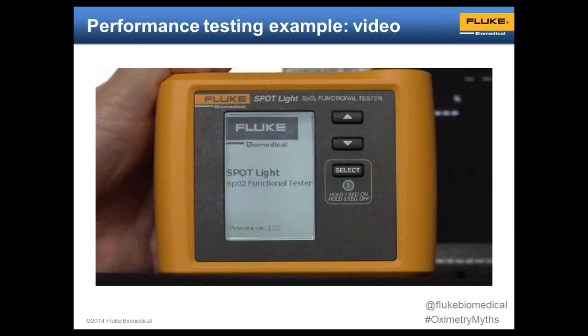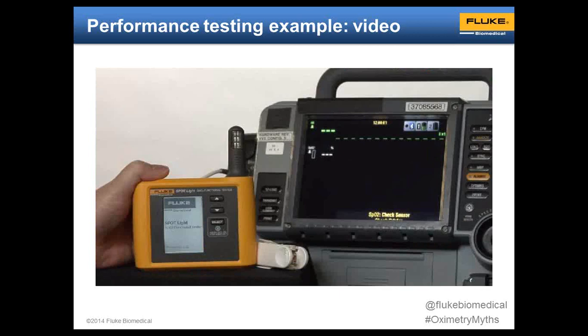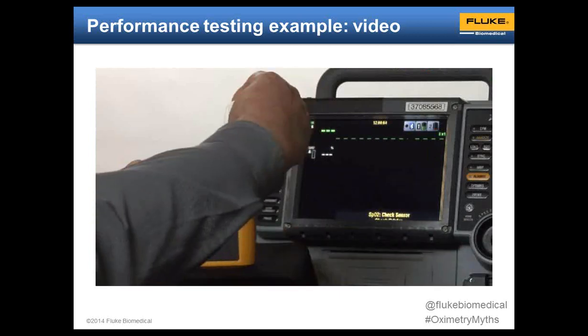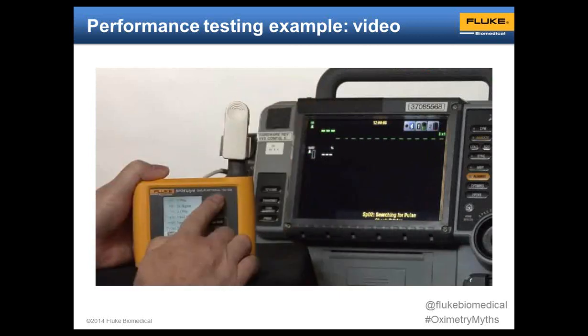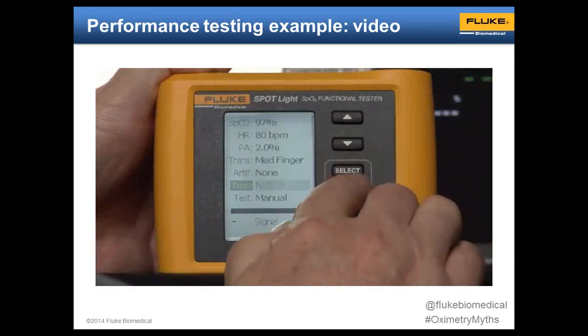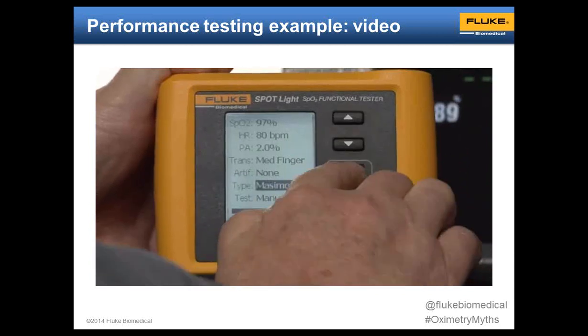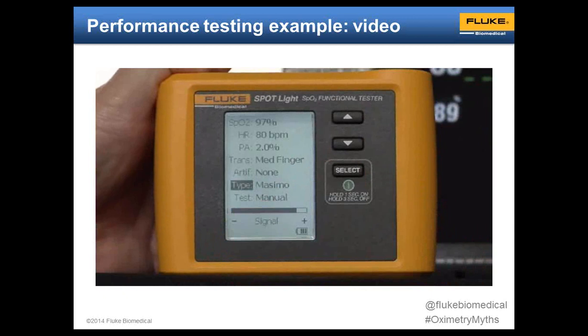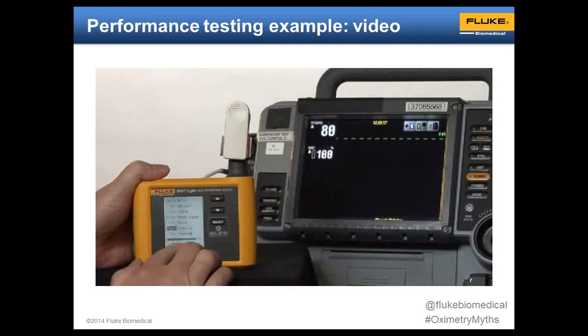Then we need to make sure that we select the right R curve or the right manufacturer. Most of the functional testers will have a number of R curves built into them, and you need to check the manual to make sure which R curve to use. Note that some manufacturers license SpO2 technology from other companies. So just because you have a certain type of monitor does not necessarily mean that it's the same for the SpO2 or the R curve installed in the device. So check the manual to learn about that.